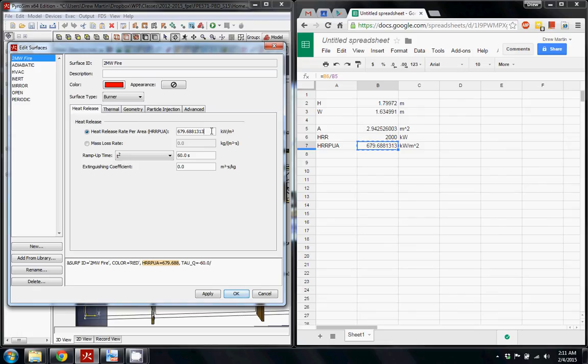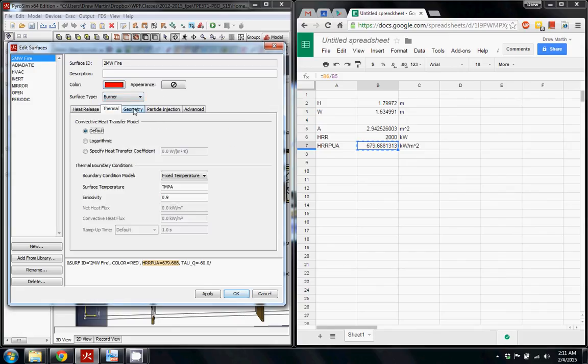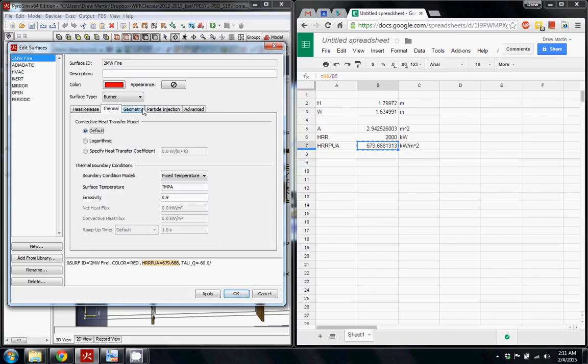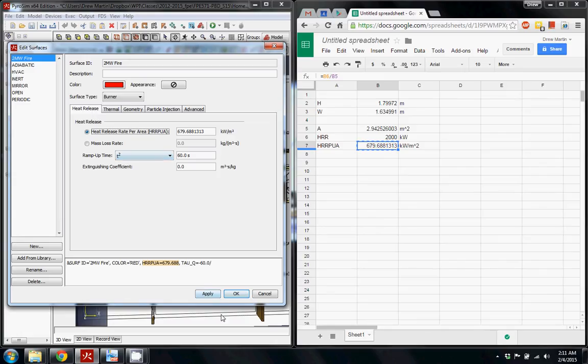FDS will account for fluctuations and flame pulses and different amounts of oxygen as air flows through it. It'll fluctuate a little bit, but it should be around 2 megawatts. So that's how you input the design fire for a 2 megawatt T squared fire and a burner. The rest of these things are up to you.